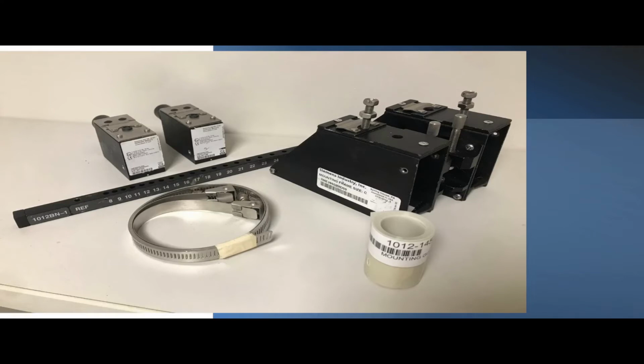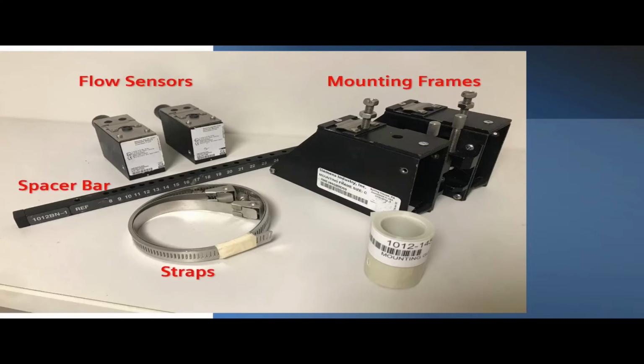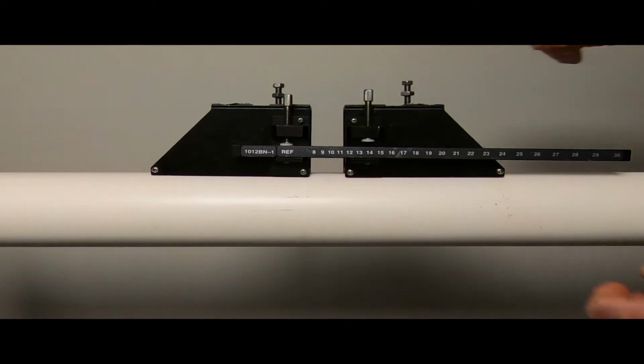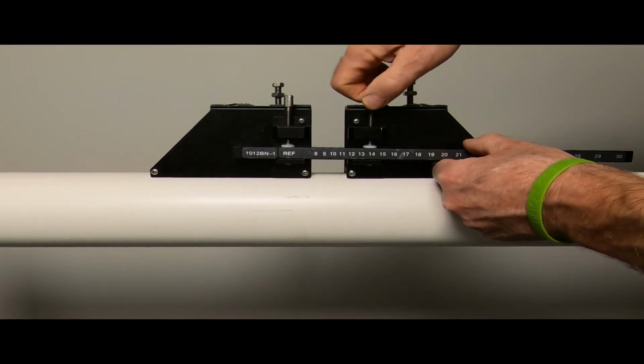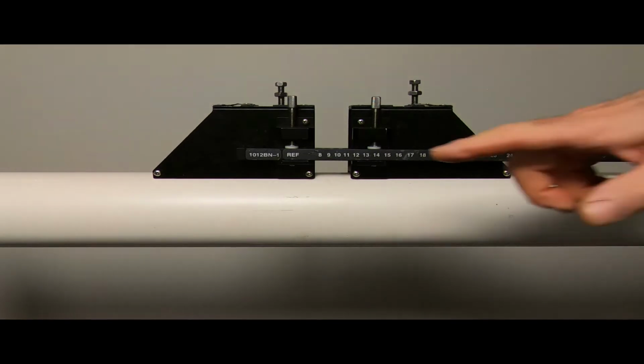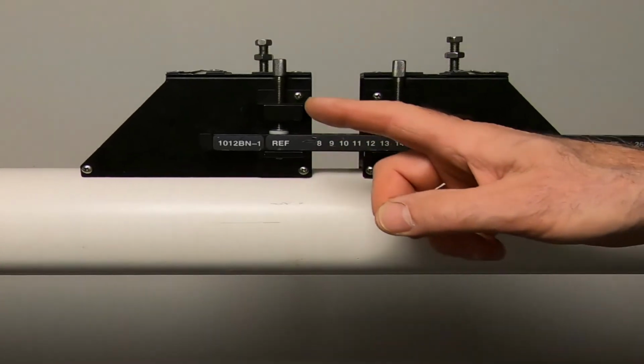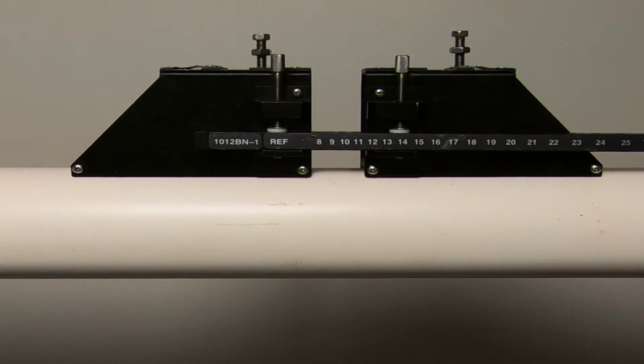When you receive your ultrasonic flow meter, along with the flow meter electronics, you'll receive the sensor mounting kit. This includes the flow sensors, the mounting frames, the spacer bar, and the straps required for the size pipe you'll be installing on. In addition, you'll also get this little gem. This is known as the mounting guide, and this is what's going to help us install our flow sensors in direct mount. So let's head on out to the pipe and get started. We'll begin by attaching our mounting frames to the spacer bar at the spacing indexes indicated by the flow meter when we programmed it. In our case, that would be spacing index 14. Therefore, we have one frame at reference, one frame at 14, and we've established the correct spacing for our pipe in direct mount.